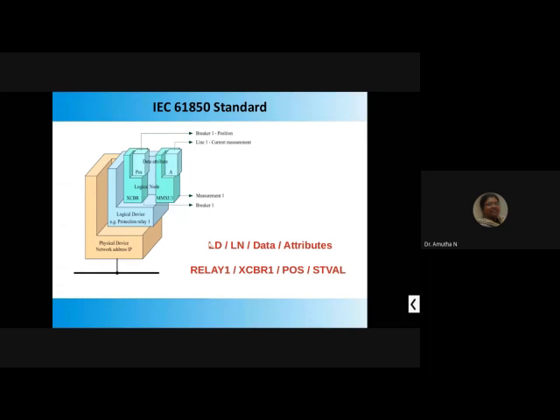It will be in this form: first it identifies the logical device, next it identifies the logical node, and then it identifies which type of data. Even the circuit breaker may have other data, like oil temperature data, and that information will be sent as data. Data attributes show whether it is high, low, or like 1, 0. It is usually communicated as relay 1, XCBR for the logical node, and data position—for example here it is position, and this is the attribute, a status value.